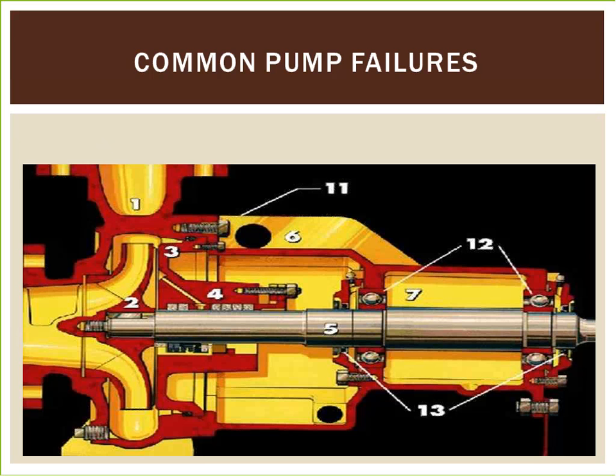Both the pump and the drive have shims, shown as number 13, and/or bearings, number 12. Degradation over time will lead to irregular sounds and high temperatures. Proper maintenance is crucial to extending the life of this equipment. Daily rounding is a great way of discovering irregular sounds promptly. Quick response to these situations will minimize damage and can avoid replacement of equipment.